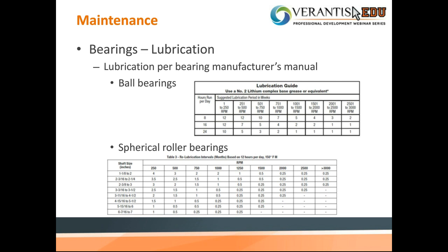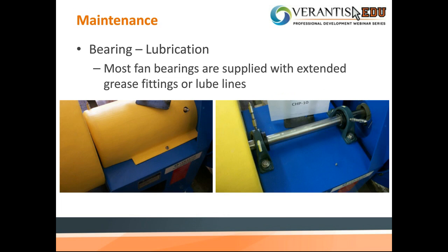So for bearing lubrication, most fan bearings are supplied with extended grease fittings or lube lines. If that is not an option for your new fan, make sure you let the OEM know. That way you don't have to remove the canopy or remove the belt and shaft guard, and you've actually got access to it right there. It just makes lubricating bearings after service that much easier.